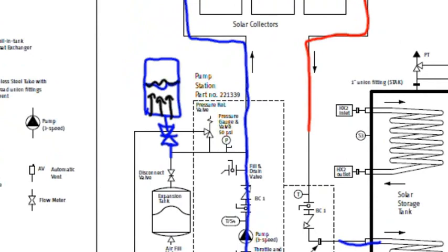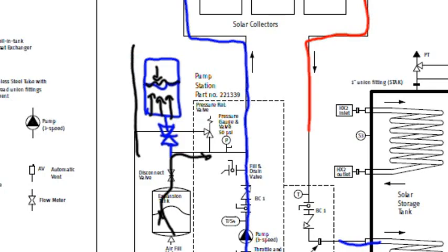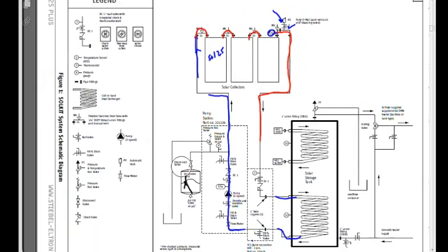Even with that bladder ripped or torn, I will still keep that air up here to keep it pressurized. Whereas if it tears down here, that air is going to work its way into the system. So some folks like to keep that expansion tank on the top side. That's just personal preference for how some of it goes.